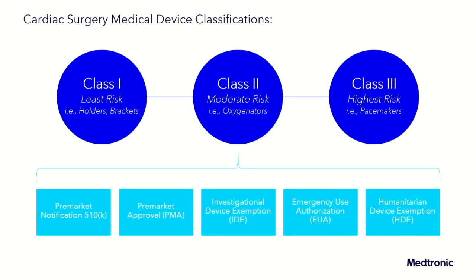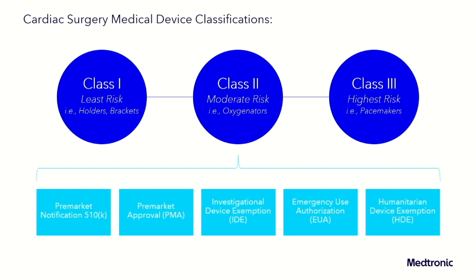Then when you look at the PMA, or the pre-market approval, that's what the class 3 devices fall under. They are the highest risk, and so they do require scientific evidence, which is typically done in the form of clinical trials. So you might ask, why did we not have devices for ECMO previously? All of the ECMO devices before 2016 fell into this class 3. So big clinical trials were required. No one in industry was going to be able to provide that level of support to get those devices approved. We also have investigational device exemptions.